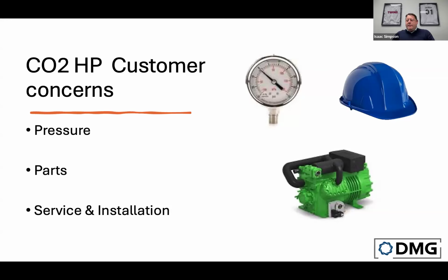Looking at our commercial installations, it's been used on the refrigeration side—thousands of very popular name-brand stores we all shop at are using CO₂ in their refrigeration systems for cold storage, walk-in, and reach-in units. Those pipes are in tens of thousands of facilities across North America that we visit every day to get our groceries. These systems are widely deployed, so that operating pressure isn't something to be concerned about.